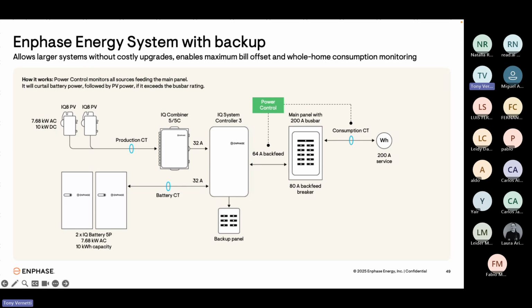Yep, absolutely. And that's made possible with power control system technology, because we have consumption CTs located here, and a CT on solar and battery as well. So everything is measured, which means we can allow the solar and battery system to function at their maximum capabilities while also ensuring we don't export any power back to the utility grid.